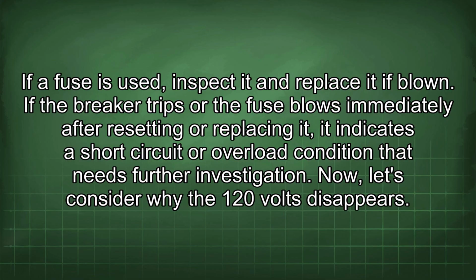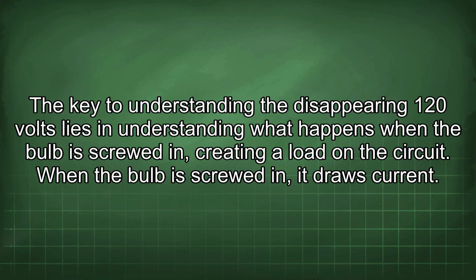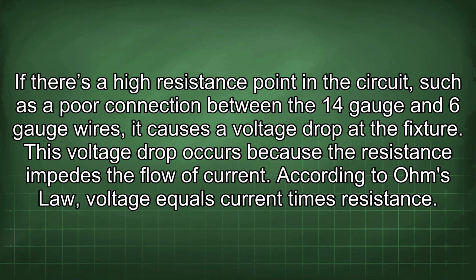Now let's consider why the 120 volts disappears. The key to understanding the disappearing 120 volts lies in understanding what happens when the bulb is screwed in, creating a load on the circuit. When the bulb is screwed in, it draws current. If there's a high resistance point in the circuit, such as a poor connection between the 14-gauge and 6-gauge wires, it causes a voltage drop at the fixture.